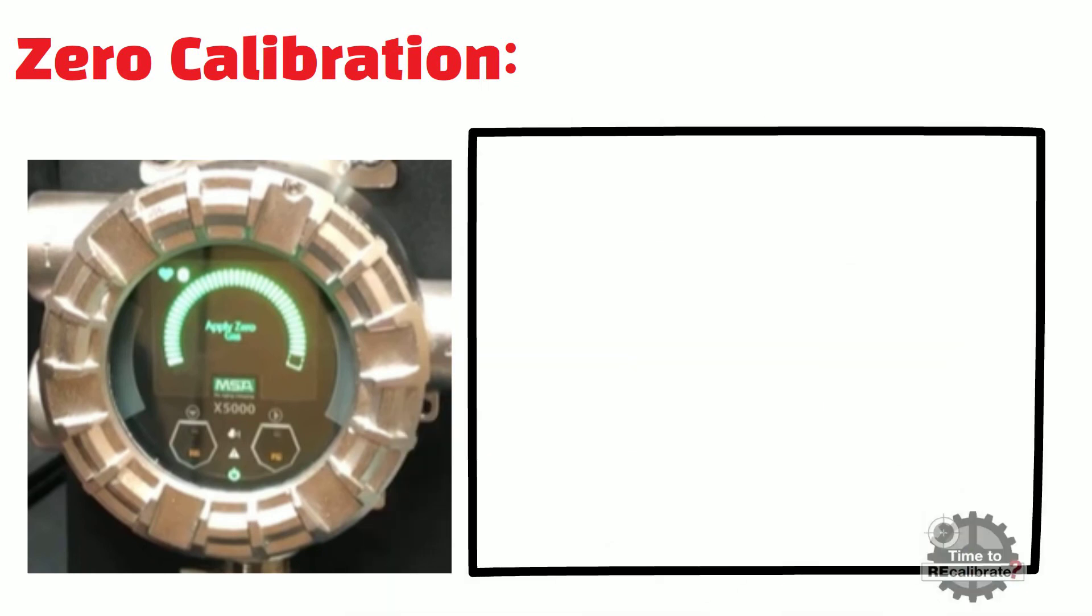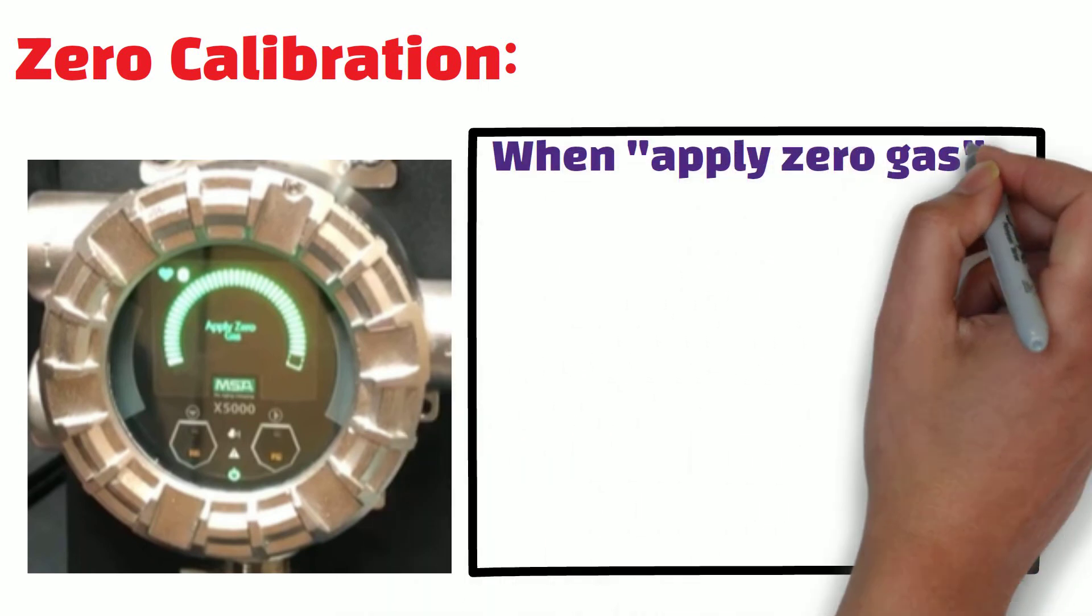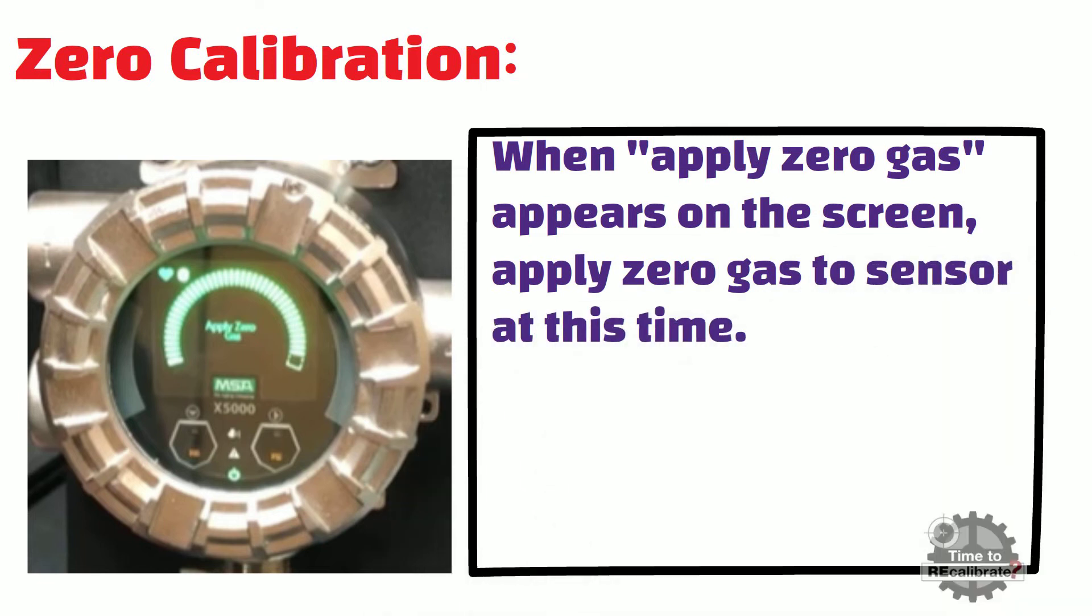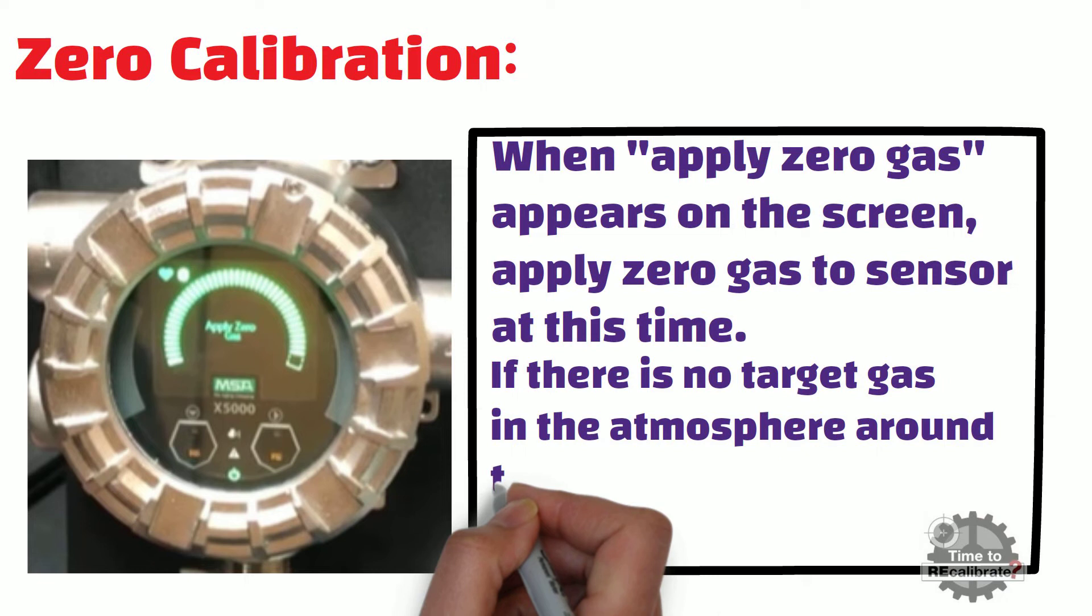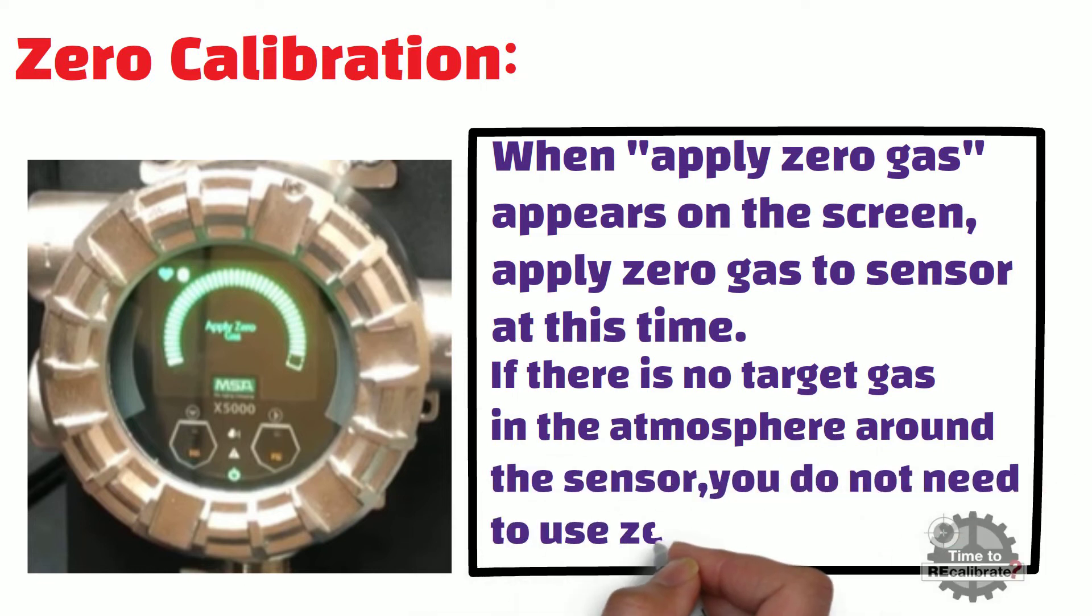When you see apply zero gas on the screen, apply the zero gas to the sensor. And if there is no target gas in the atmosphere around the sensor, you do not need to use zero gas in this case. Zero calibration will occur in open to air.